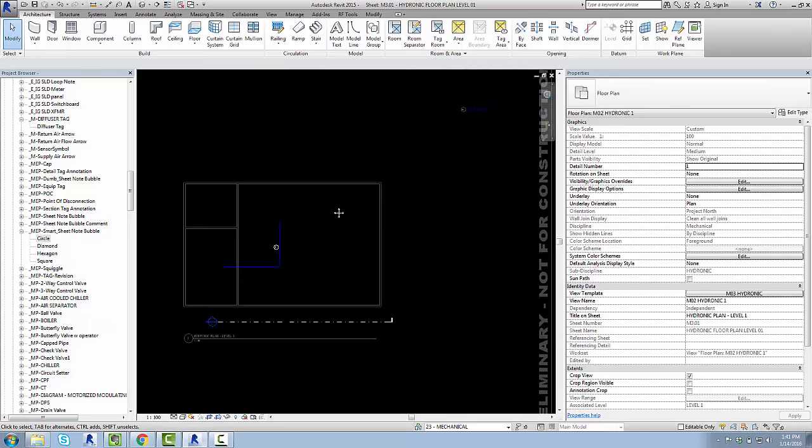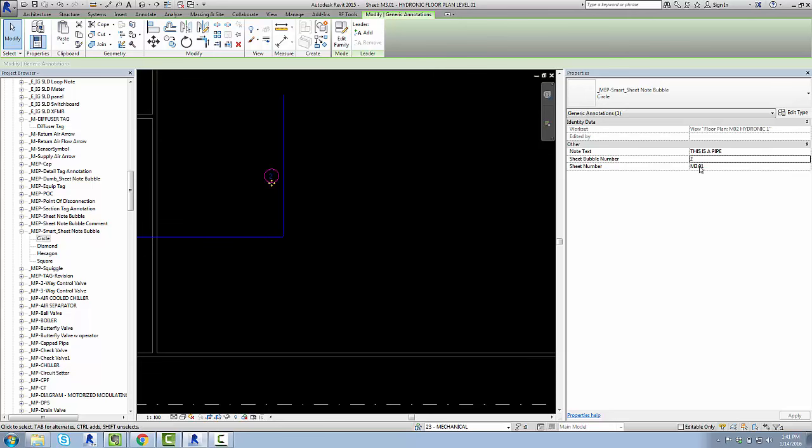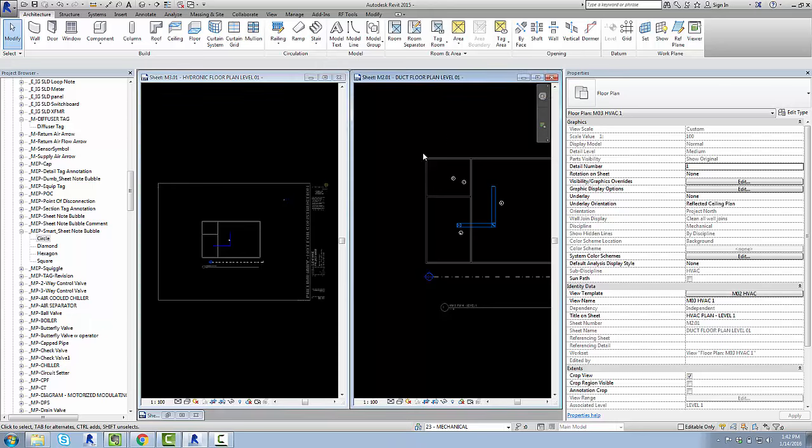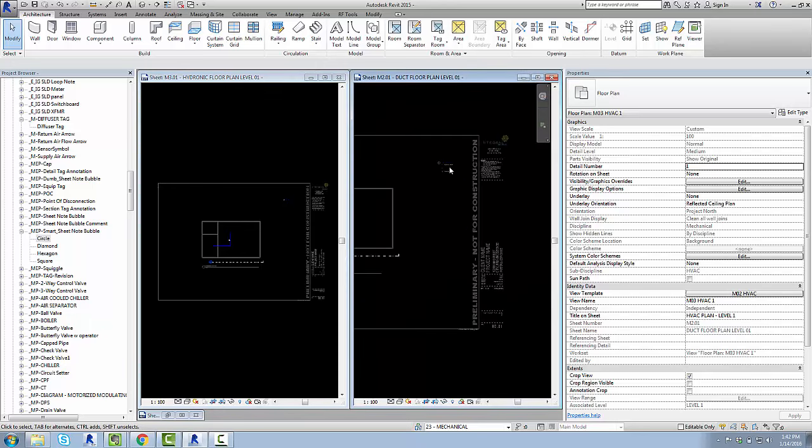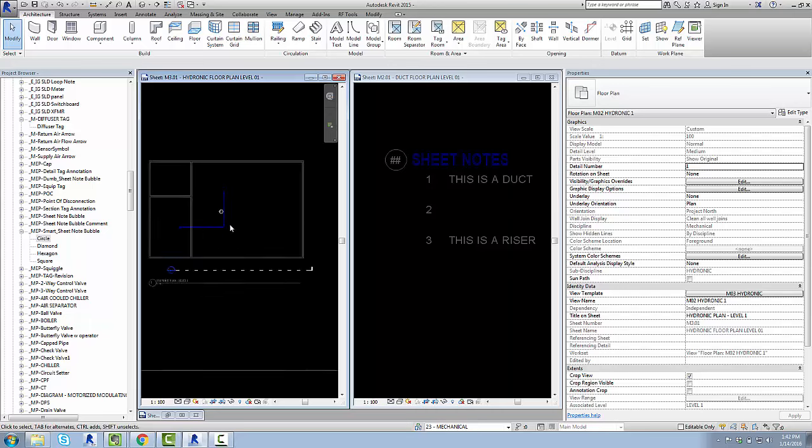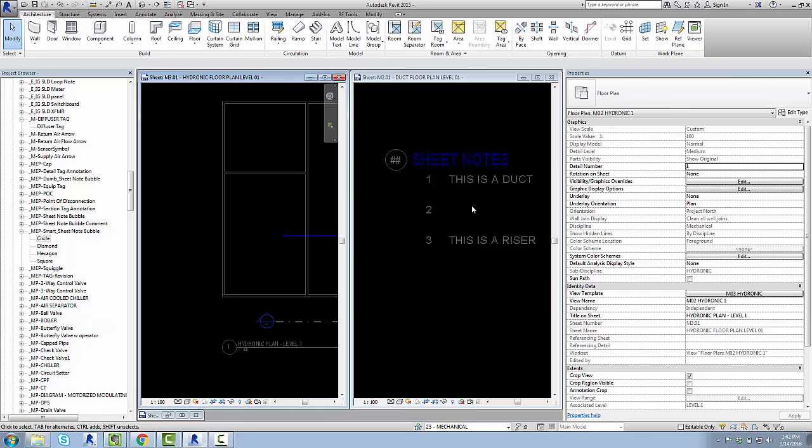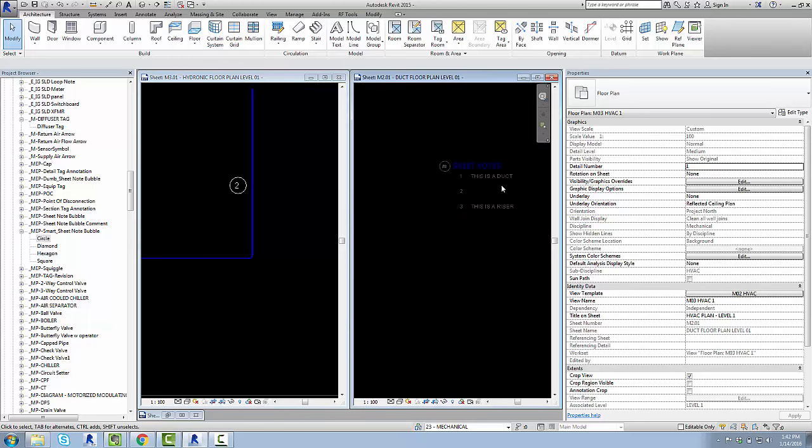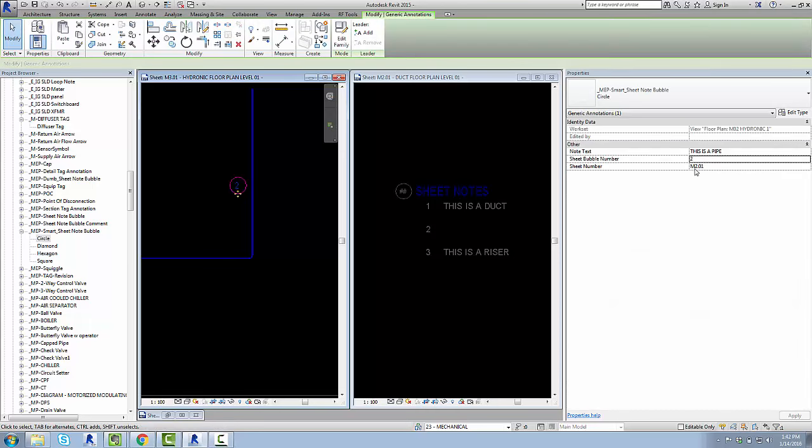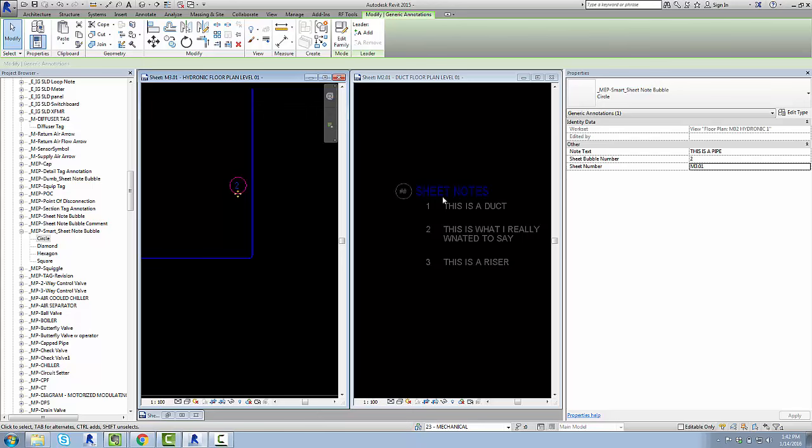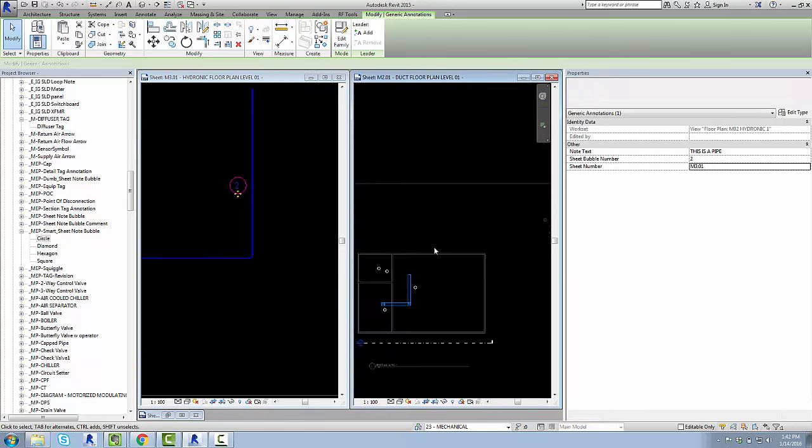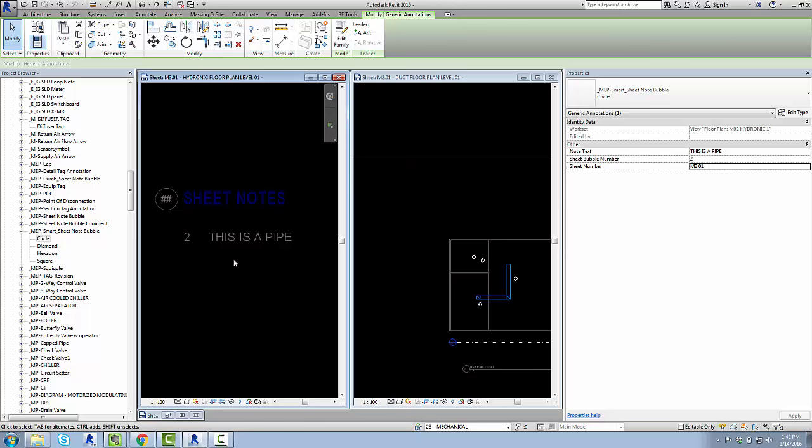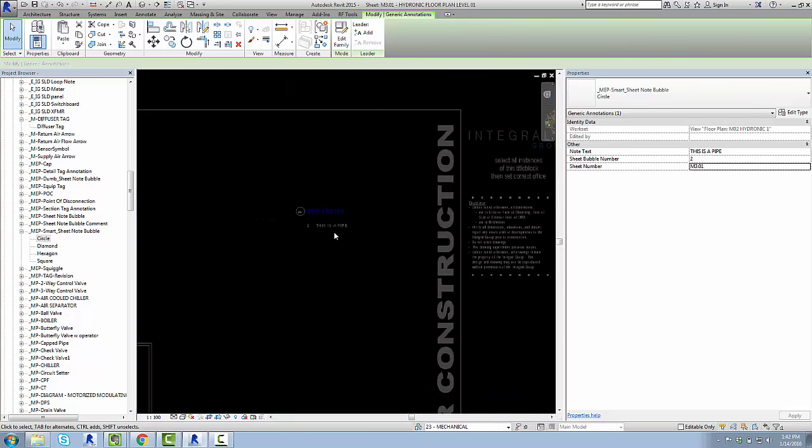But it's not showing up here. And I'm like, well, why isn't it showing up here, that's super messed up. Well, the reason is because the sheet number's M201, it's a sheet M301. Well, let's look back at M201, you'll notice two is blank again. It's because over here, you know, this schedule isn't reading sheet note bubbles from just this view, it's reading sheet note bubbles anywhere, and that's why we need this parameter that says sheet number M201. Again, it tells the sheet note schedule which of these guys to look up. So, that's fine, all I do is change this guy to M301, and then my M201 schedule fixes itself, because now it's just reading these two guys. And now, over here, this one is reading it correctly.